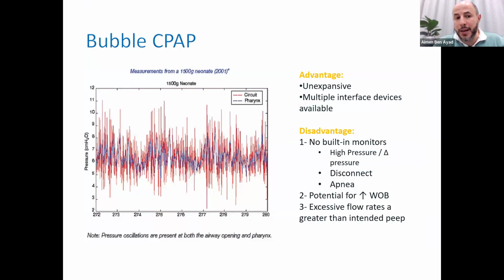What's the advantage of the bubble CPAP? It's inexpensive, it's easy. Multi-interface devices can be set on it, but it has a disadvantage. Another advantage is it has an oscillatory pressure. Although it's being in the middle, you can see a high frequency oscillatory pressure on the bubble CPAP.